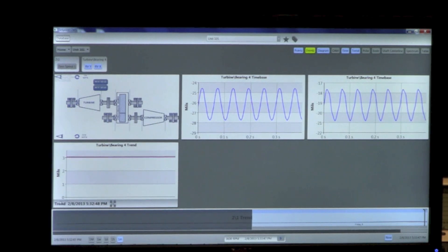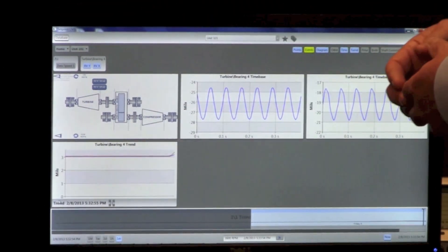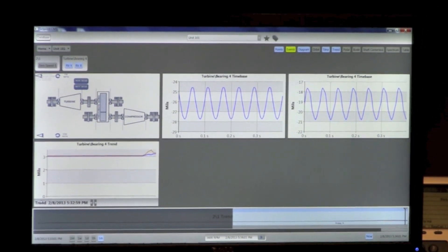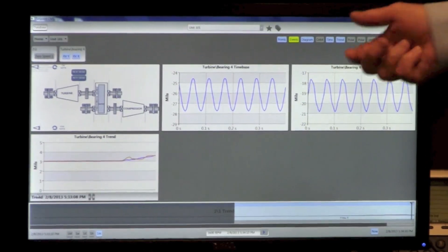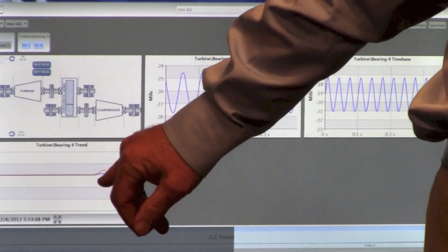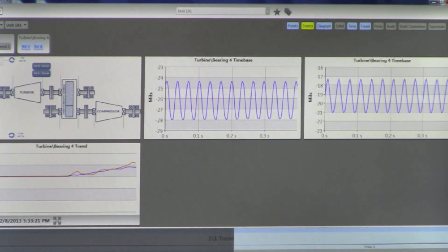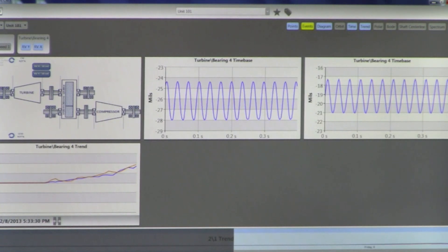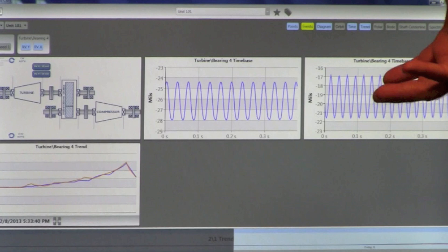Cho is going to go ahead and speed up our rotor kit. You'll hear the rotor kit accelerating. The way our system is currently configured, we're grabbing one waveform every 10 seconds, so we'll be able to see the waveforms increase in frequency and decrease in period. We'll see the shape change slightly as the shaft accelerates, and we can see our trend graph increasing the two overall vibration levels for the two channels we're showing here as the rotor kit continues to accelerate. Cho, slow us down a little bit — as we decelerate, we should see the amplitude go back down and the waveforms decrease in frequency with the period increasing.